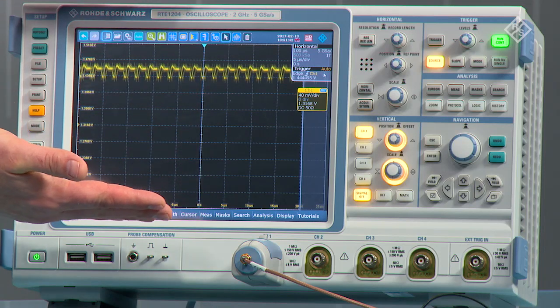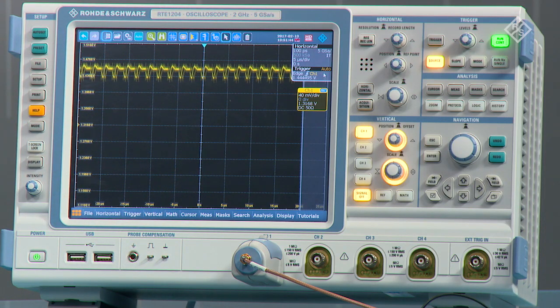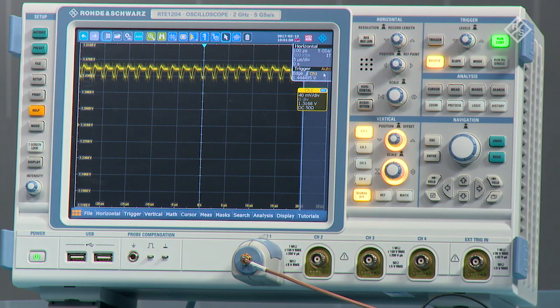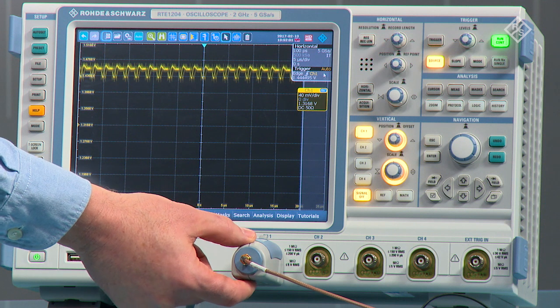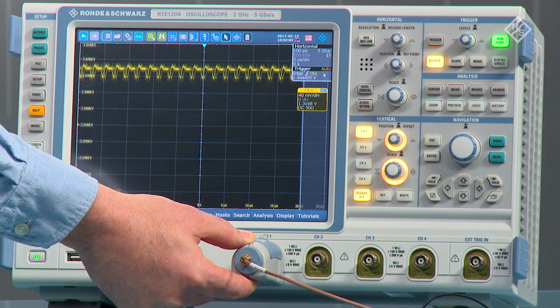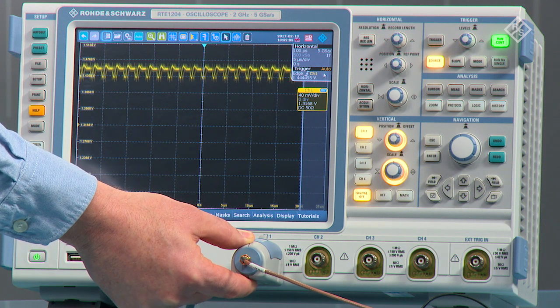Second, achieve sufficient offset. Scopes typically don't always have enough built-in offset to allow users to place the waveform at the center of the screen and expand. Blocking caps or using the AC coupling mode on the scope will remove the low-frequency DC components. This solves part of the problem, but it eliminates the ability to see true DC values and drift. Look to solve the problem using a probe that has built-in offset. In this case, the ZPR20 has plus or minus 60 volts of offset to center the signal.